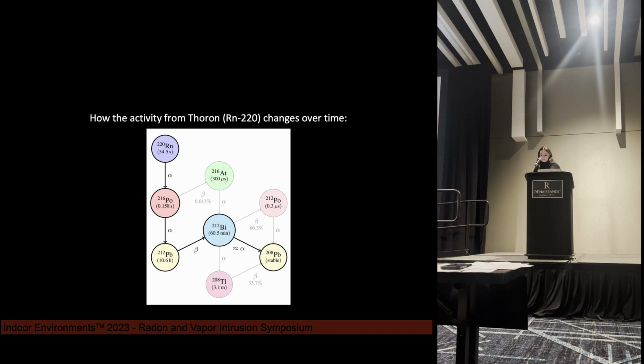Radon-220 has a half-life of about 1 minute. When radon-220 decays, it will decay into polonium-216. Immediately afterwards, polonium-216 will decay into lead-212, which has a half-life of 11 hours, and it is a beta emitter. The sniffer does not detect beta, therefore, the alpha activity of radon-220 will be nearly completely gone within the first 3 minutes. Essentially, within the time that I've been here speaking to you, if thoron was present, all recognizable activity would be gone.